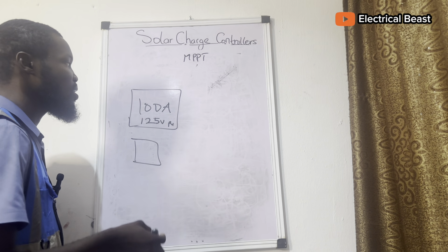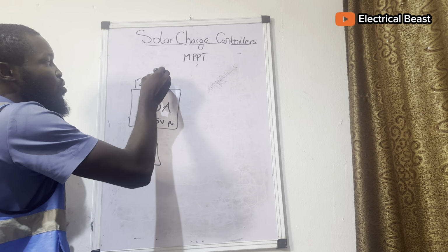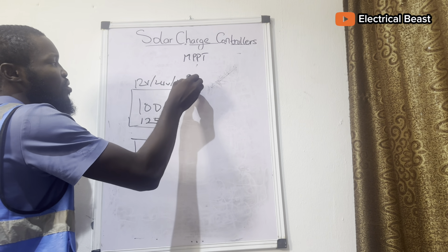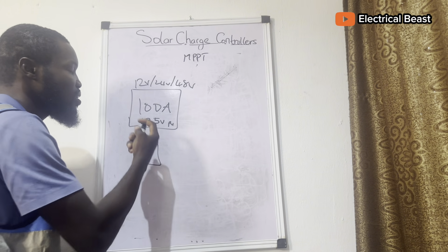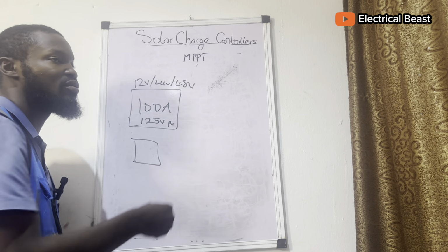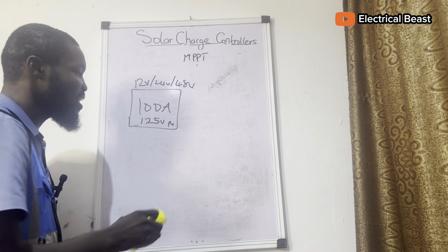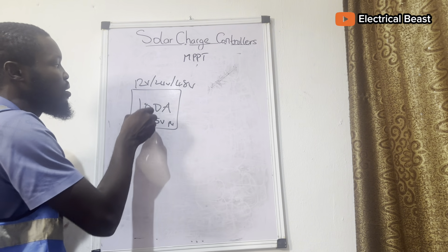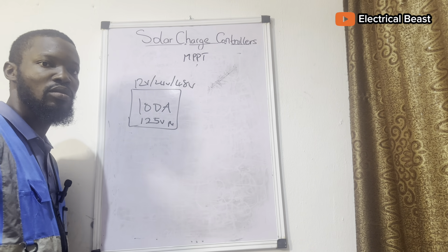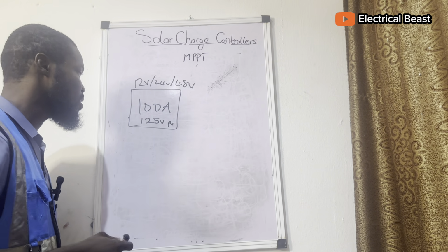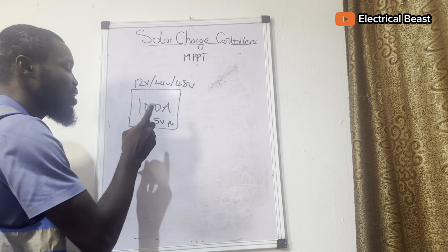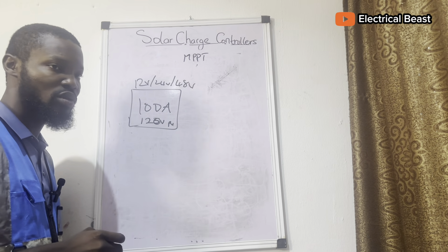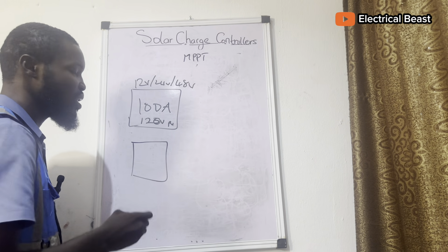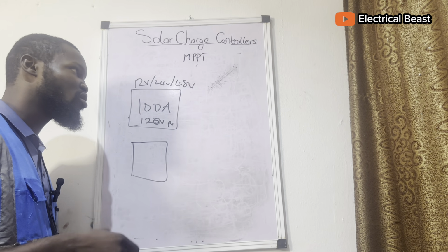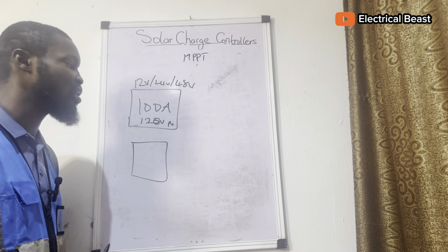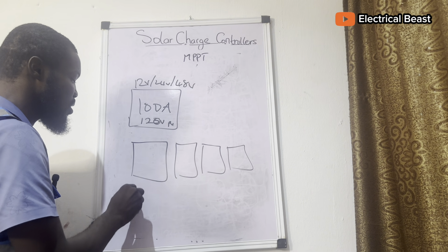Most MPPT controllers work with 12 volts, 24 volts, and 48 volts. You can work with 12 volt, 24 volt, and 48 volt systems, provided whatever you are connecting is within the range of this specification, the current and the voltage. Now, let's say we have 120 volts, then you'll be looking at 48 volt panels. 48 volt panels from around 400 watts and above. You can have up to 6 solar panels.